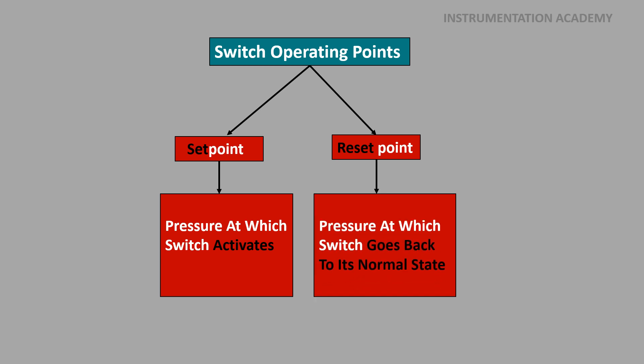The variation in pressure does not change the status of the switch until the set point is reached. When the set point is reached, the switch changes its state from NO to NC or NC to NO, and remains in the changed state until the pressure drops below the reset point.